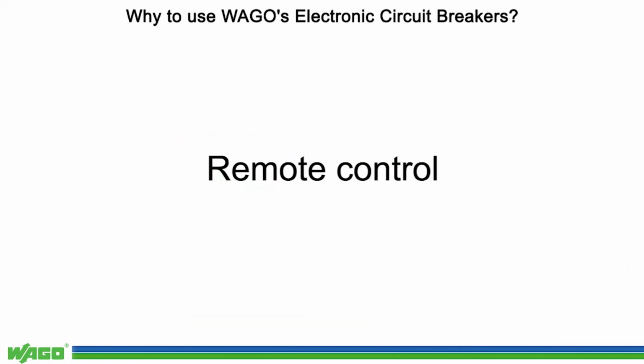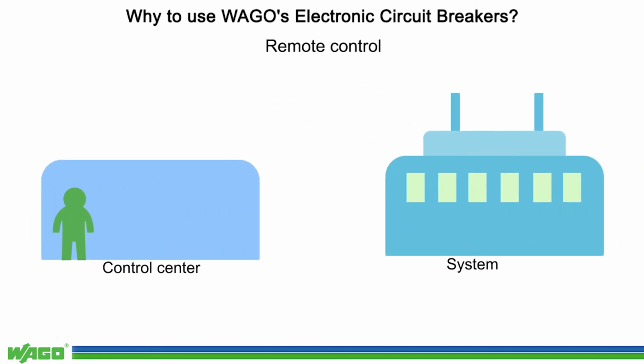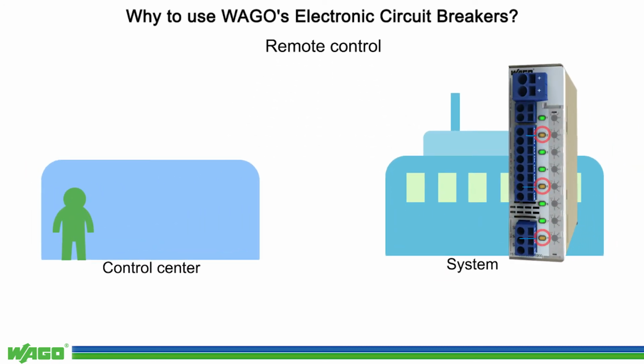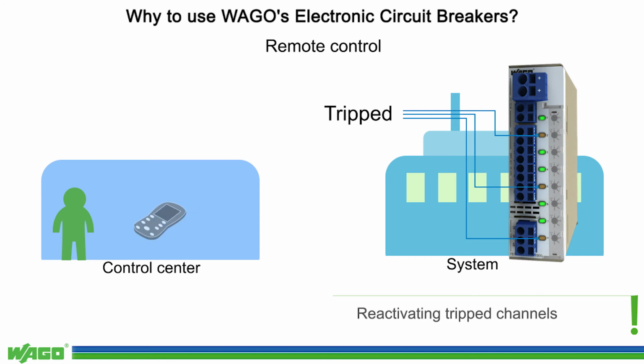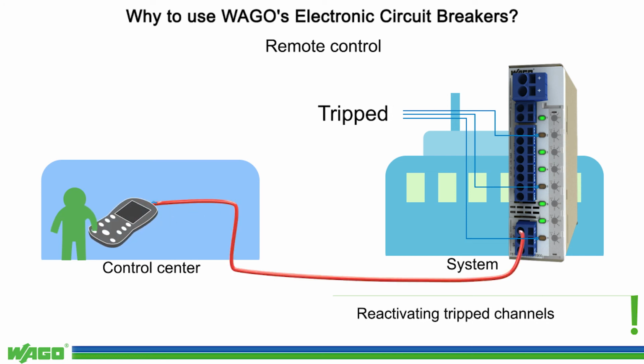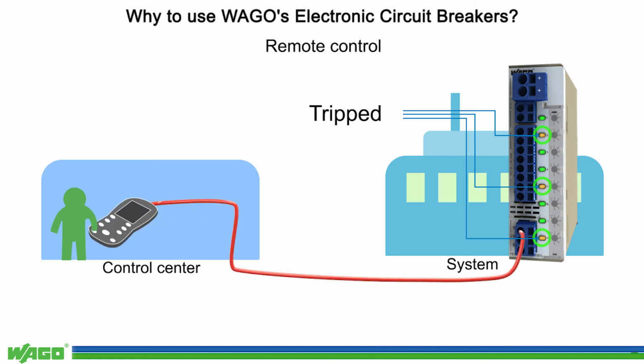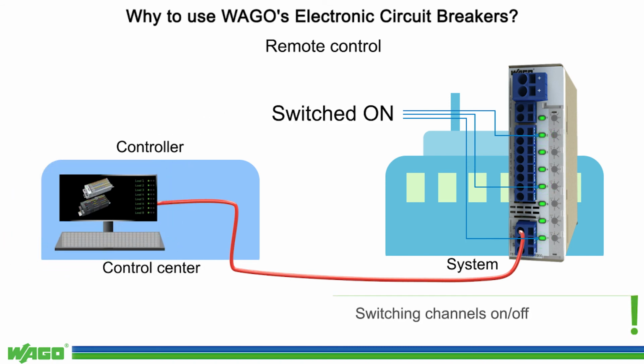ECBs can also be controlled remotely. This allows, for example, tripped channels to be switched on again from outside the system. A connected PLC can switch on or off channels arbitrarily when needed via the communication.